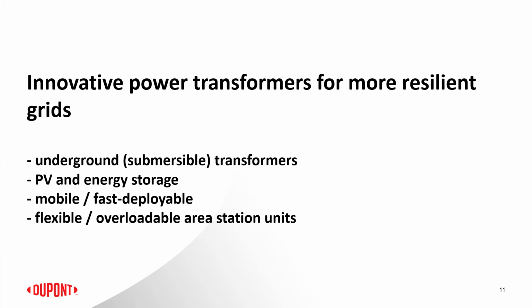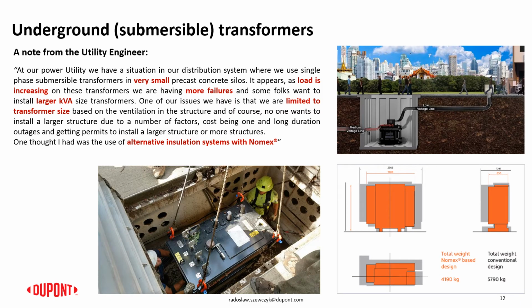And then moving to the examples of the applications for the alternative insulation system. One example is presented here. This is for the underground submersible transformers and the distribution substations. This is based on the historical concept of the compactness enabled by the high temperature insulation system based on Nomex. So in case of such substations, there is pretty much confined space for the transformer, limited space, and in case of need for the replacement, the new unit must fit the existing space in the existing installation. The problem becomes real if the utility needs a transformer of larger electrical size. So that's a real example.